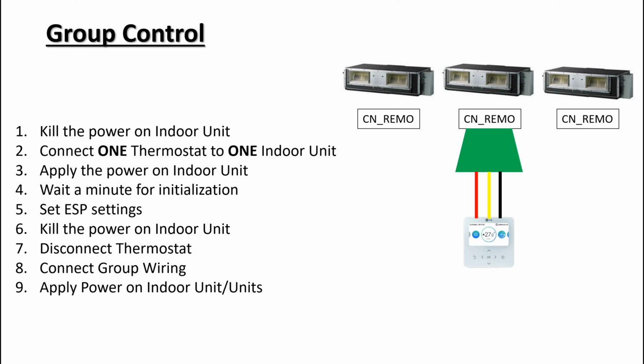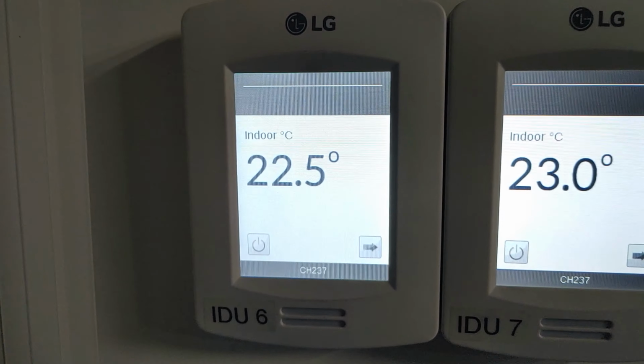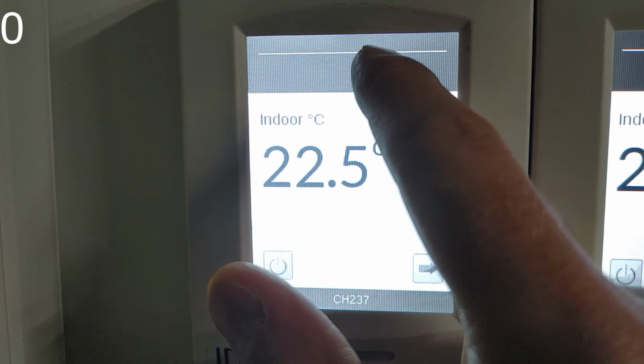Here is step-by-step detail on how to do that. Make sure you kill the power, connect one thermostat to one indoor unit, then apply power on the indoor unit, wait about a minute for initialization, set up your ESP settings, kill the power, disconnect thermostat, then reconnect all group wiring back and apply power on indoor units. Done!